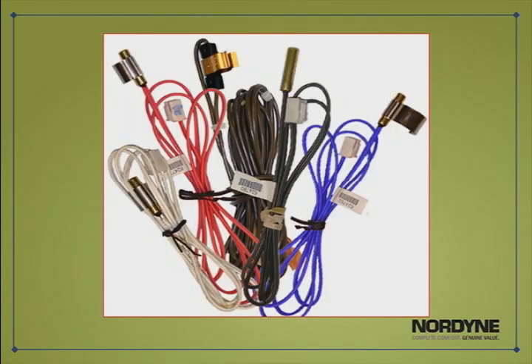All 5 sensors are 10K ohm resistors and can be checked using an ohm meter. Each sensor is also color-coded for easy identification. The reversing valve is energized during cooling or during a defrost cycle in heat mode. The valve solenoid receives a 24-volt signal from the interface board. The power line filter prevents electrical noise from leaving the unit. This filter is also paired with the reactor coil to prevent electrical spikes entering or leaving the unit.